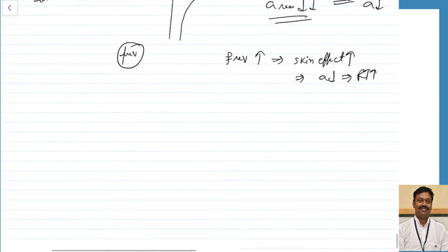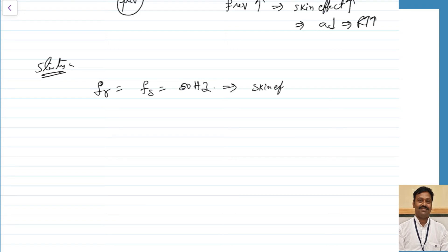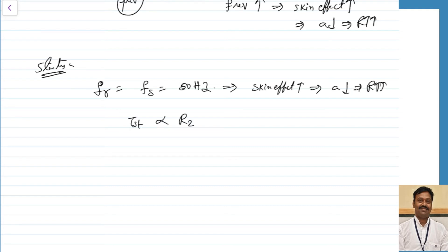At the time of starting, the rotor frequency equals the stator frequency of 50 Hz. At this high frequency, skin effect is maximum, effective area is minimum, and resistance is very high. Since starting torque is proportional to R2, a very high R2 leads to a very high starting torque, giving excellent starting performance.